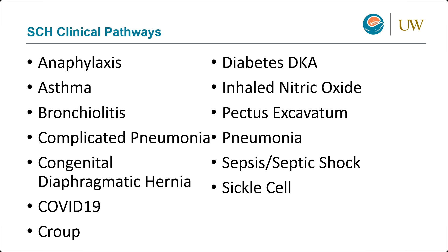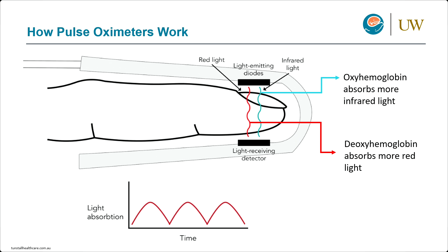Let's say you have a pulse oximeter wrapped around your finger. At one end is a diode that emits light, namely two wavelengths, red and infrared light. On the other end is a detector that looks at how much of that light passes through the finger and is absorbed at the other end. We know that hemoglobin that is attached to oxygen, oxyhemoglobin, absorbs more infrared light, and hemoglobin that is not attached to oxygen, deoxyhemoglobin, absorbs more red light. So as these wavelengths pass through the finger and are absorbed on the other end, the detector looks at the ratio of infrared to red light and uses that to give you an oxygen saturation.